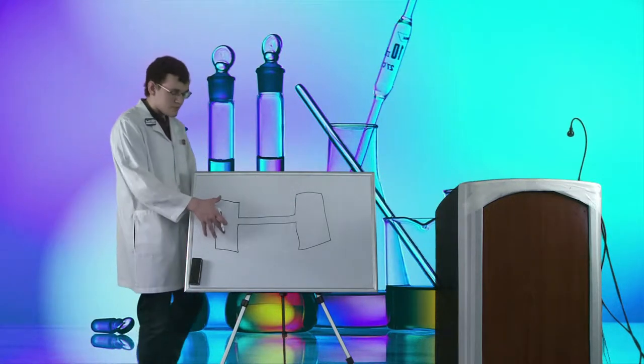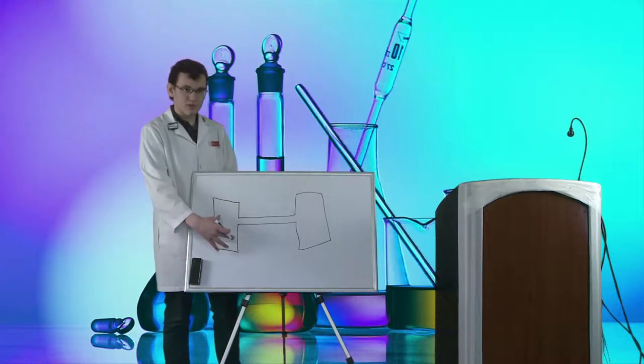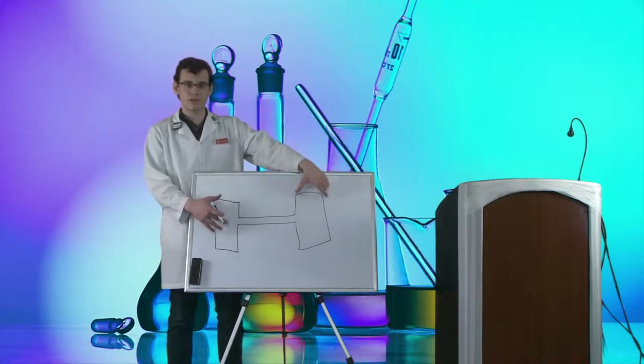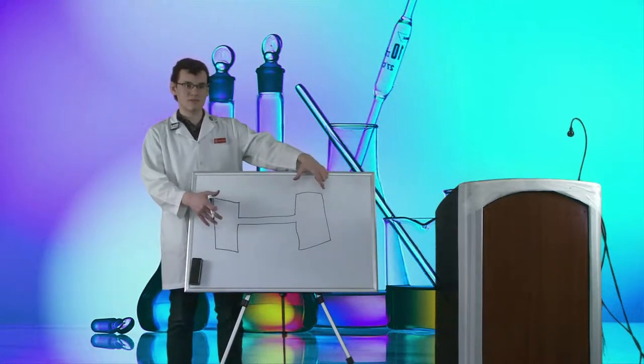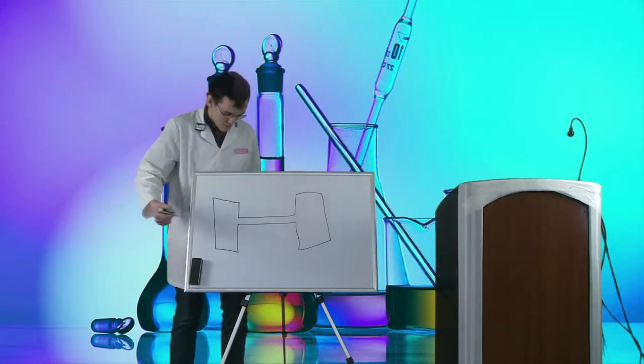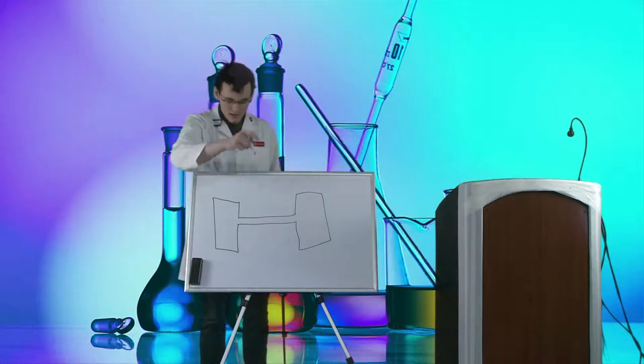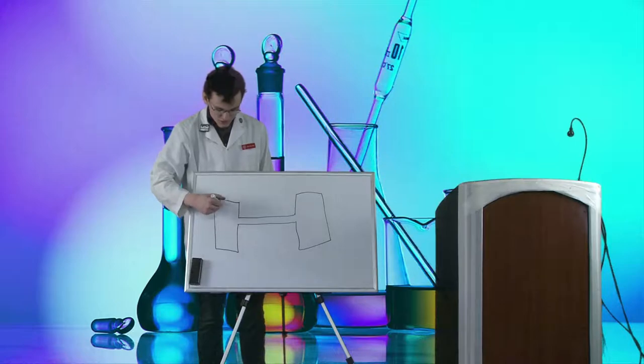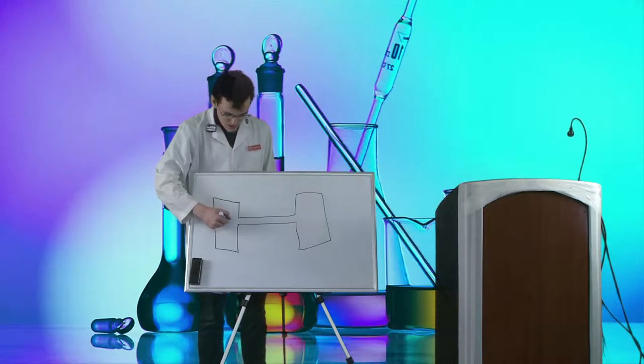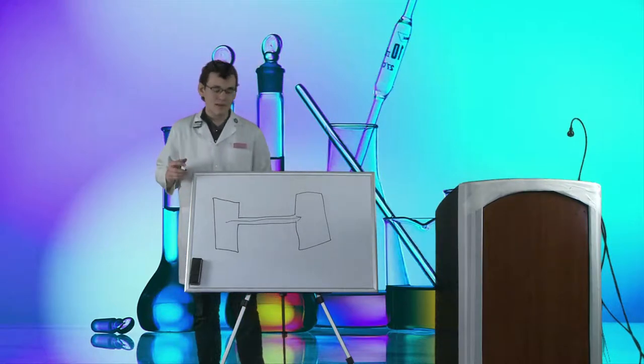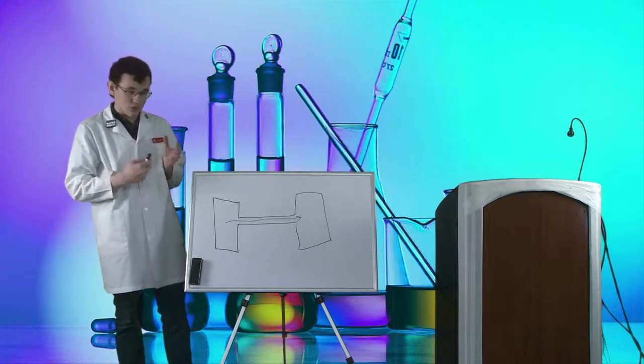Now for molecular flow: same setup but 10⁻⁶ Torr pressure on one side — a few air molecules bouncing around, almost never touching each other, just bouncing off the chamber walls. What are these air molecules going to do? They're going to act like light — like rays. One air molecule traveling up here bounces off the chamber wall, bounces off another wall, and slowly bounces down the pipe until it eventually gets to the end. Because there are no other air molecules to force it, it's just bouncing off the surface. That's molecular flow.